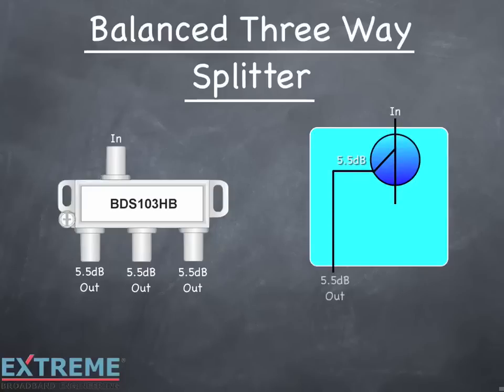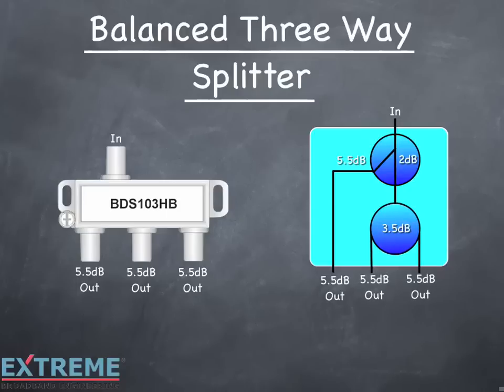Now let's look at a balanced three-way splitter and how it's constructed. On the left is a balanced three-way splitter where each port has 5.5 dB of loss. On the right, let's build the symbol equivalent. We start with a 5.5 dB directional coupler. The tap leg, which loses 5.5 dB, feeds directly to one of the 5.5 dB ports. The output port of the directional coupler loses 2 dB, so in order to get an additional 3.5 dB of loss, we add one two-way splitter off this leg for a total loss of 5.5 dB on the other two legs. Now each port has 5.5 dB of loss.